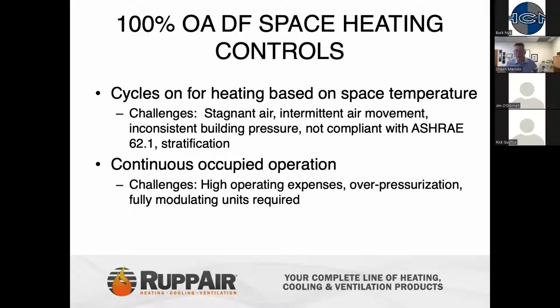So 100% outside air is used for direct fired heating is done. The biggest thing to know about from the control side is that when 100% outside air direct fired units are used for space heating, they will have some cycling characteristics to them. Either they'll have to cycle on and off, almost like a unit heater, or they'll have to be continually operating and modulate the burner, but continually bring in outside air.